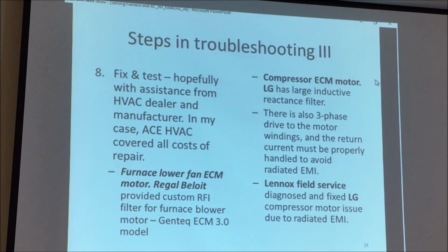There's also a three-phase drive to the motor windings, and in that case, you have to be careful that the current is properly handled, or you can also get radiated EMI. So Lennox diagnosed and fixed the LG problem due to radiated EMI, and I'll explain how in a minute.